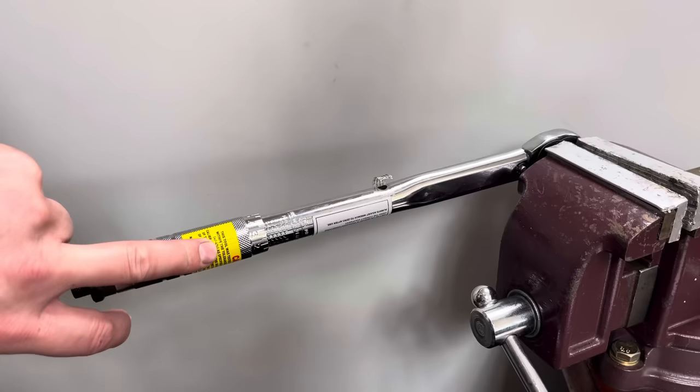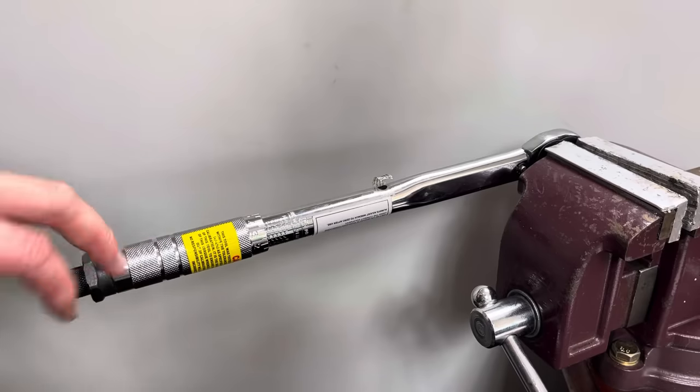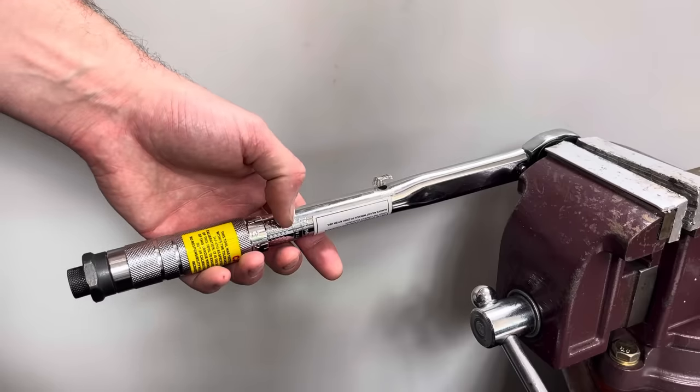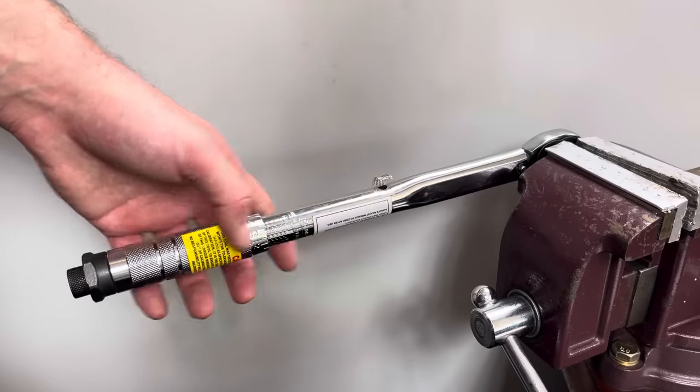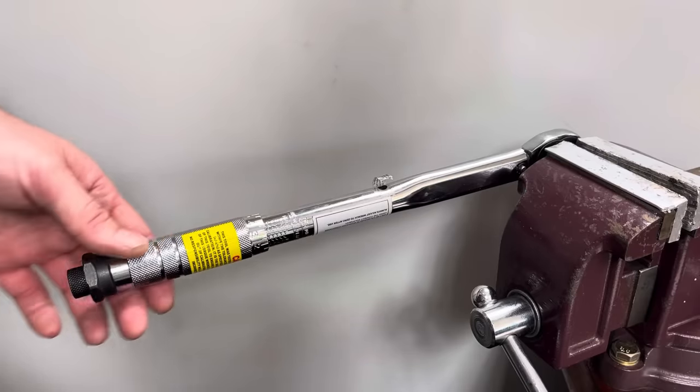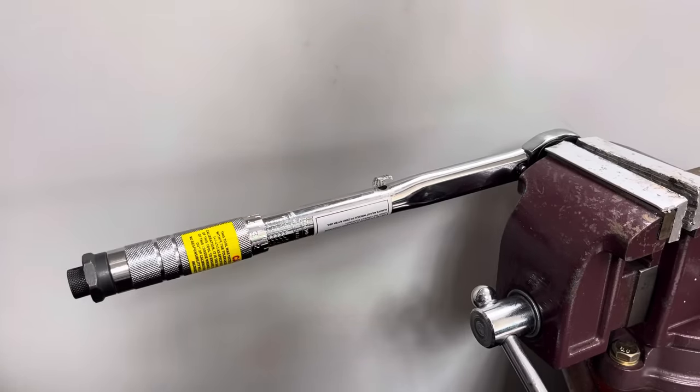This one came from the manufacturer with plus or minus four percent. So, in this position, we're perfect. We might be, if we go up to a little bit higher torque reading, it might be less accurate. And the same on the other way. So, get an average and get yourself very close. And I think you'll be very pleased with the result.